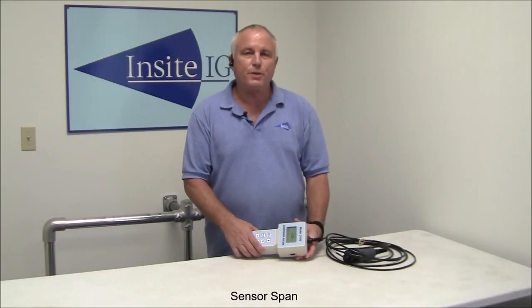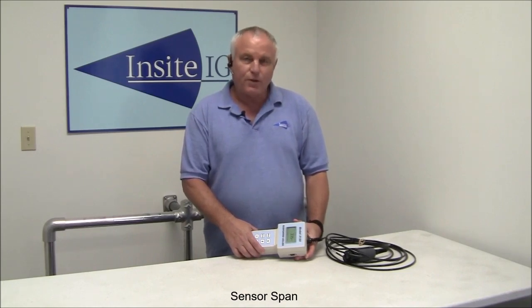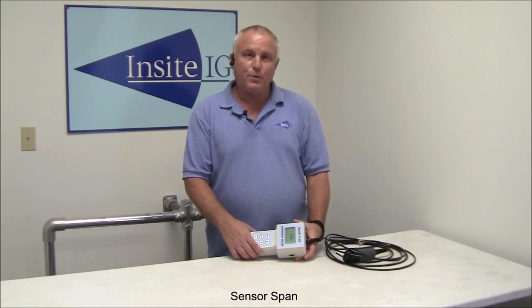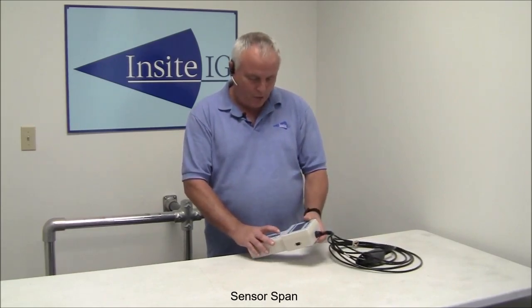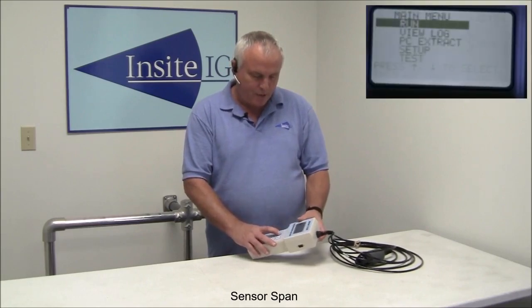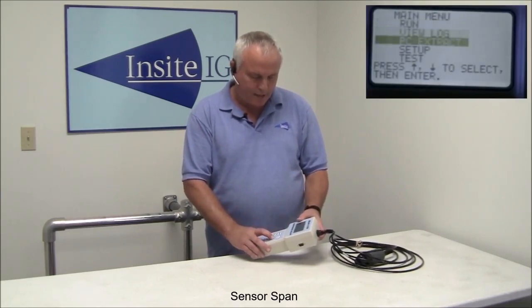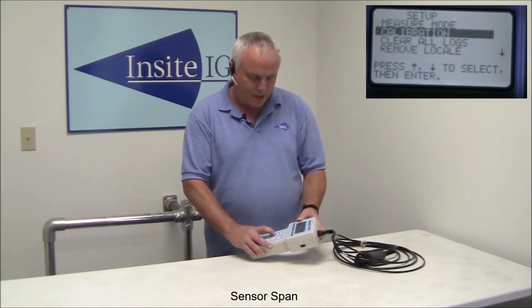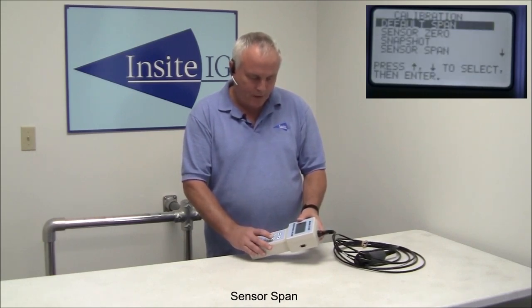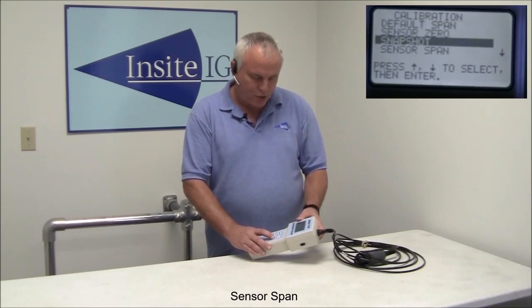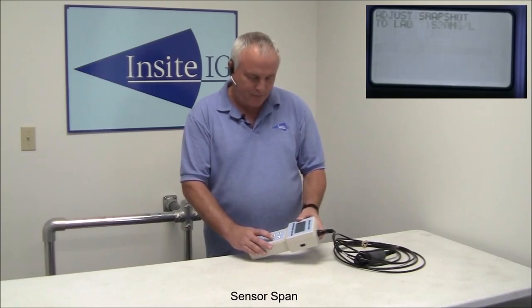The final step in doing the calibration is to do the sensor span. Once you've gotten your lab results back from the sample we took earlier when we did the snapshot, then you'll just go to the unit, turn it on, press menu, scroll down to setup, press enter. Scroll down to calibration, press enter. Scroll down to sensor span, press enter.